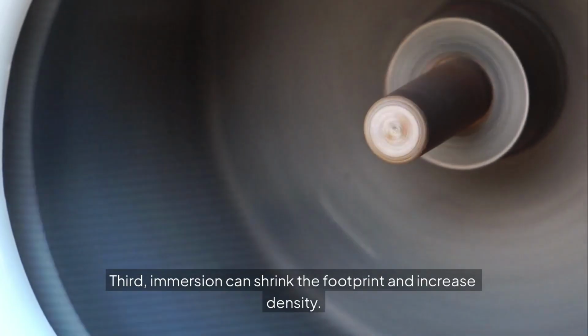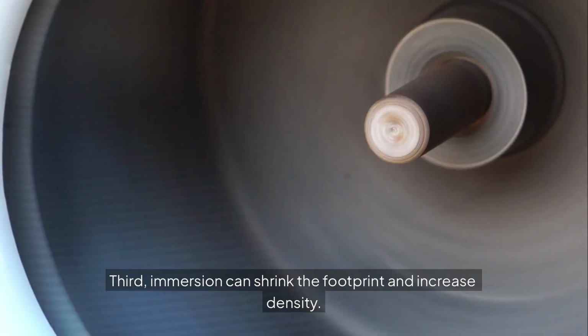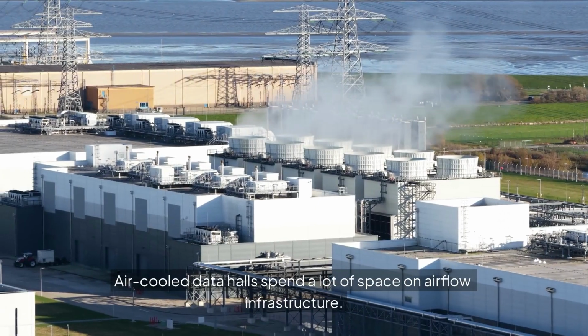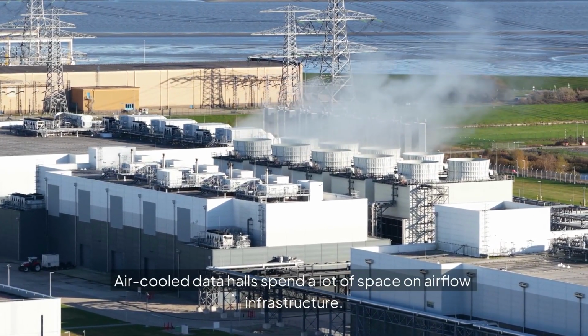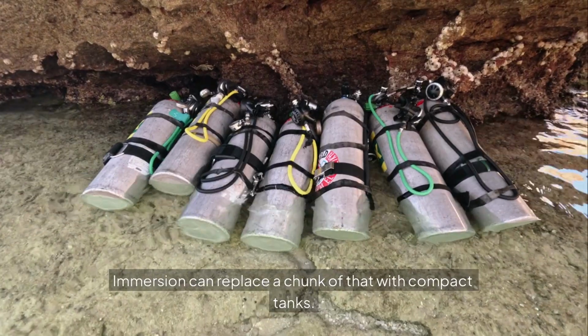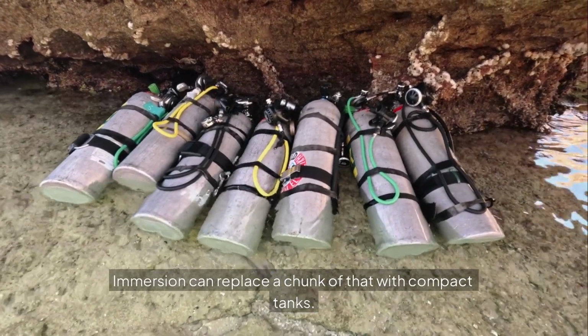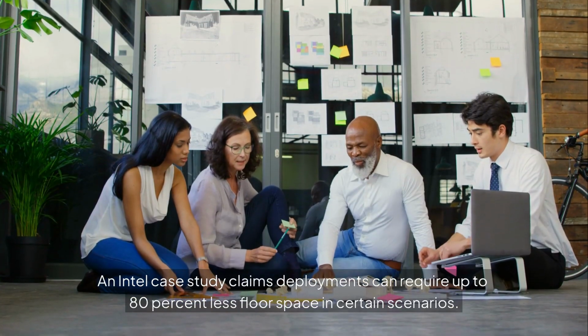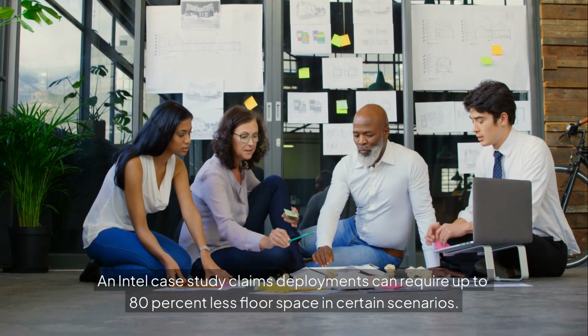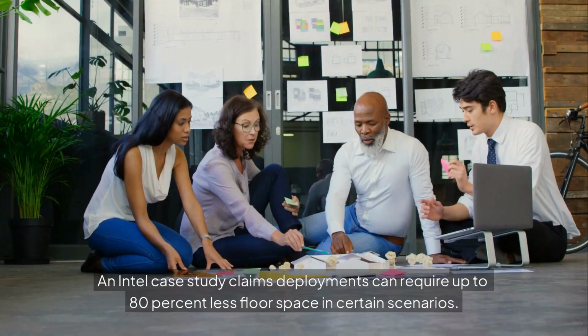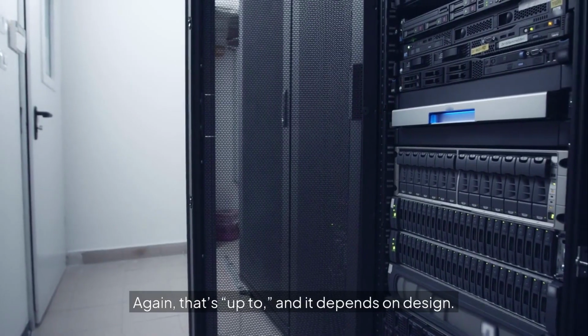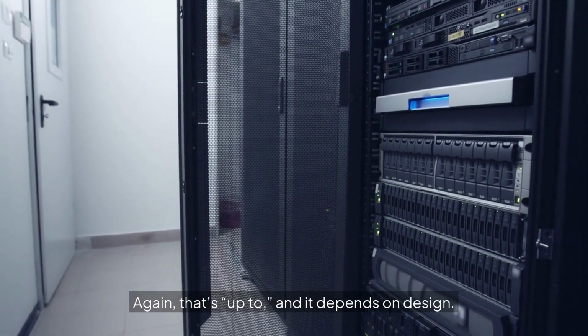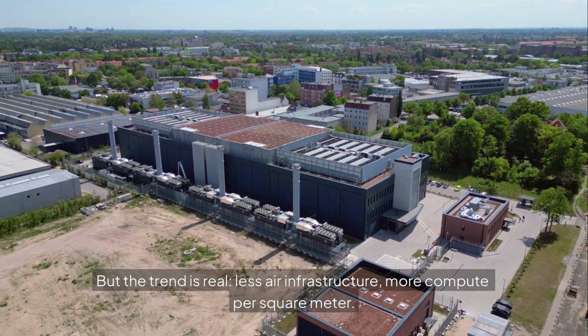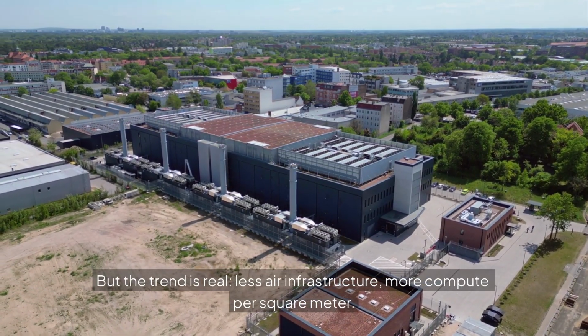Third, immersion can shrink the footprint and increase density. Air-cooled data halls spend a lot of space on airflow infrastructure. Aisles, plenum space, air handlers, and clearance. Immersion can replace a chunk of that with compact tanks. An Intel case study claims deployments can require up to 80% less floor space in certain scenarios. Again, that's up to, and it depends on design. But the trend is real. Less air infrastructure, more compute per square meter.